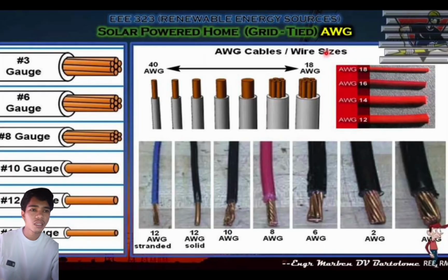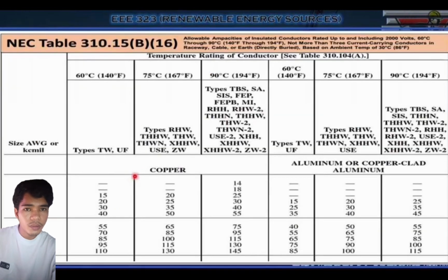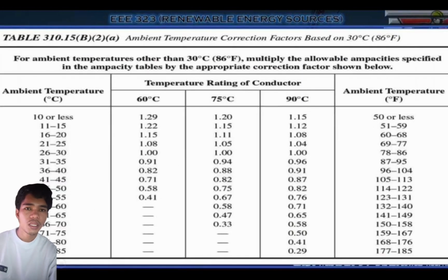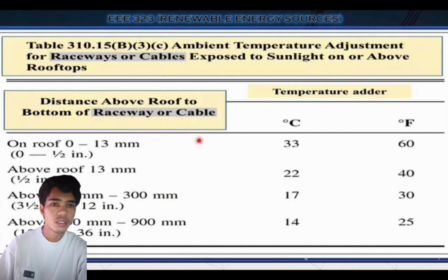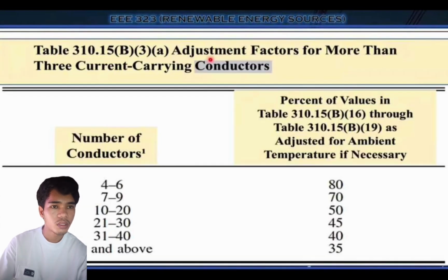Next slide, here it shows the sizing of wire. The next is NEC Table 310.15(B)(16), temperature rating of conductor. The next slide is for ambient temperature other than 30 degrees Celsius or 86 degrees Fahrenheit. Multiply the allowable ampacities specified in the ampacity table by the appropriate correction factor shown below. Ambient temperature adjustment for raceway or cable exposed to sunlight on rooftops. Distance above roof to bottom of raceway or cable. Next is the adjustment factor for more than 3 current-carrying conductors.